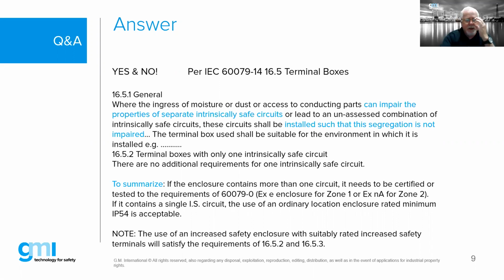Yes. So if you had just, say, a single switch in a hazardous location, and it was coming back to a junction box, we just have one loop going into that junction box, and then that junction box is carrying that circuit back to our control panel where the associated apparatus is. That junction box for that single loop is not required to be EX.